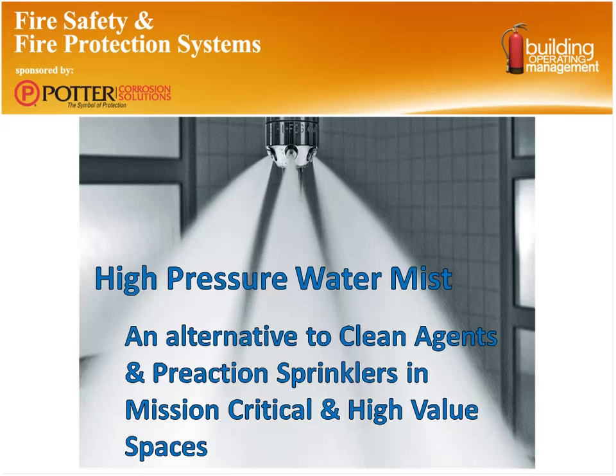And next we'll move into another technology piece, and this technology is high pressure water mist. It's not something that a lot of people are very familiar with, but it is becoming more prevalent, and as an alternative to what would have been the clean agents, systems like halons, carbon dioxide, and some of your newer FM200 and Novec products. And as an alternative to pre-action sprinkler systems, typically all of these are used in what are called mission critical and high value spaces.